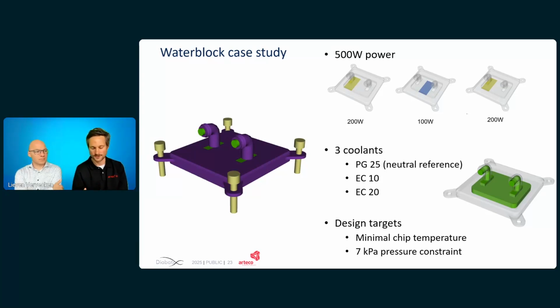Because all of the low viscosity comes from the water, and the good thermal conductivity and the good specific heat also comes from the water. So the more water you have in your mixture actually will increase and will make your fluid better on these aspects at least. Yeah.